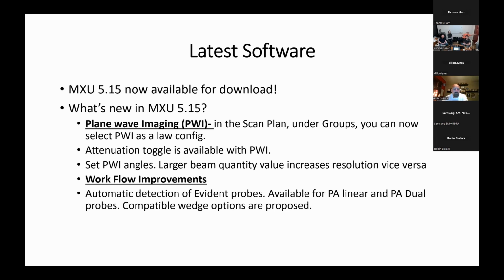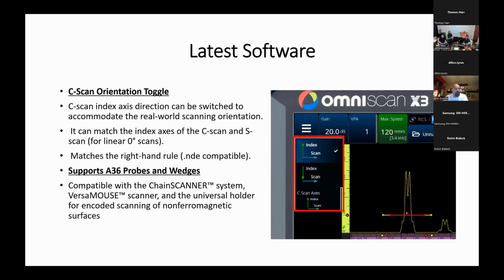Some workflow improvements: we now have automatic detection of Evident probes. So you plug in your Evident probe, you go to choose your probe, you hit auto detect, and it's able to tell what probe you have on there. It also brings up compatible wedge options, so you don't have to scroll through a list of different wedges. We also have C-scan orientation toggle available on the machine now. So if you're doing corrosion monitoring with something like Hydroform, you have that toggle available on the machine as well, and not just on the Hydroform scanner. We now support A36 probes and wedges. I actually saw this question on LinkedIn the other day. Somebody asked about it. The new 5.15 software supports A36 probe and wedge setup. So that's available now.